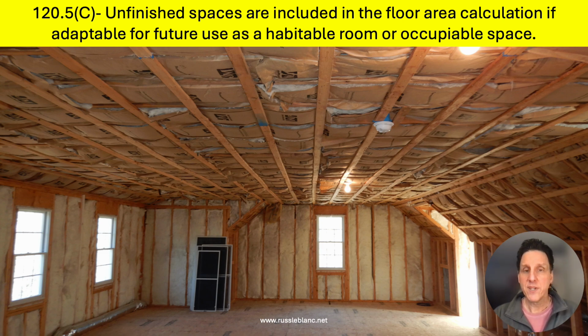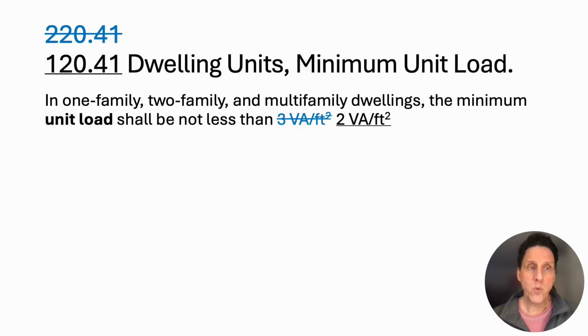Really, really big change. It could have a huge impact on the size of a service or a feeder, for example, especially for multifamilies. 120.41, formerly 220.41, dwelling unit minimum unit load. For one-family, two-family, and multifamily dwellings, the minimum unit load shall not be less than, it's now 2 volt-amps per square foot. It was previously 3 volt-amps per square foot. That's a really big reduction.